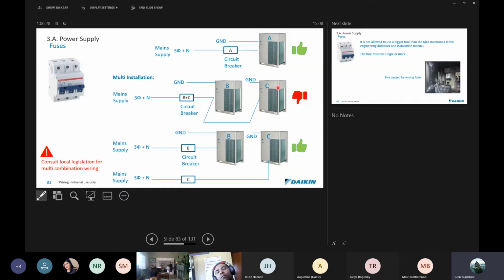One of the problems that you've got is that any fault current in one unit from something burning out or a fault can travel back through another unit. And we saw this in a job in Stellenbosch a couple of years ago where over a period of years with an old VRV2 system, they had eventually gone through a number of compressor changes and PC board replacements.